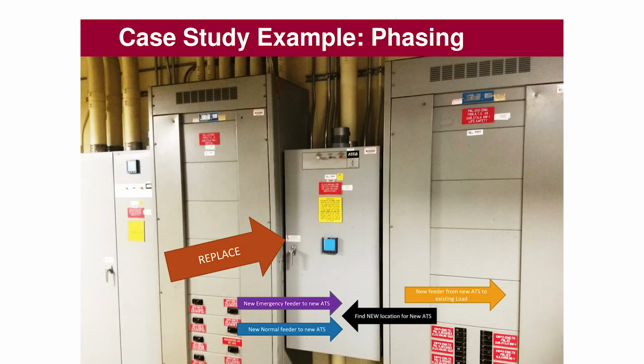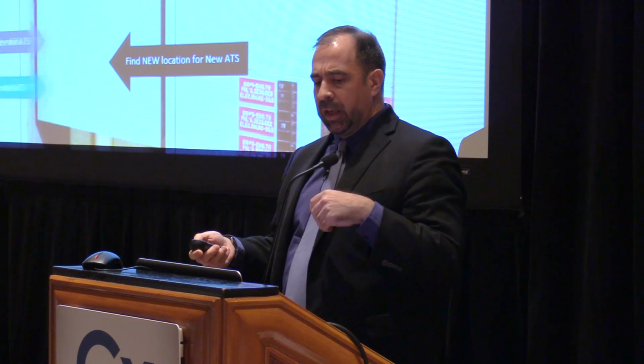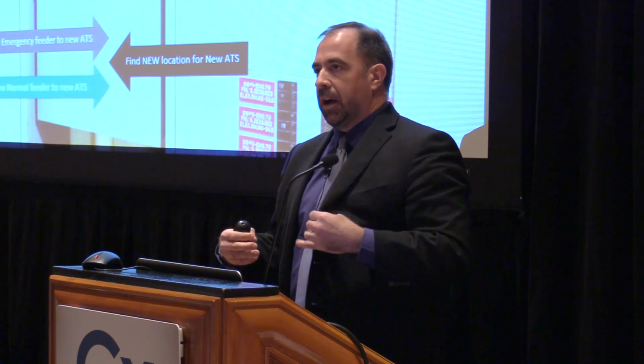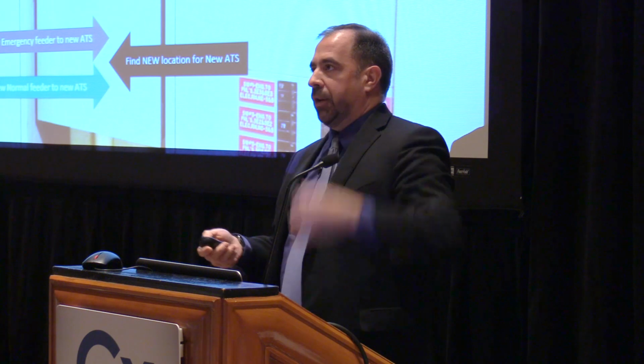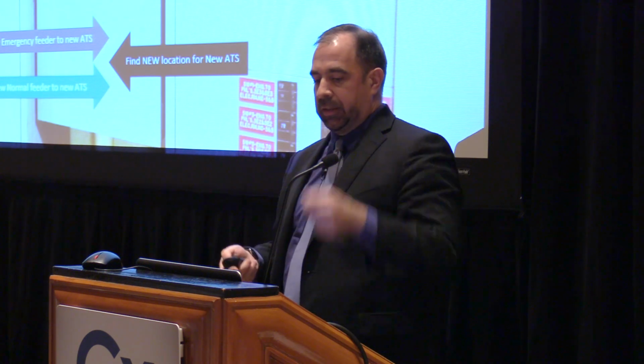The other scenario is where you can't physically put the new transfer switch in the same place as the existing one. So what do you do? You have to find another place for it. Generally, electrical rooms are thought to be very spacious with plenty of extra room, but that's not usually true. So finding a place for it is really the hardest part. But once you do, the phasing becomes easier, because you can put in the new transfer switch, make all your connections on the normal and emergency side, then run all your wire to the load, and the very last thing is disconnect and reconnect.